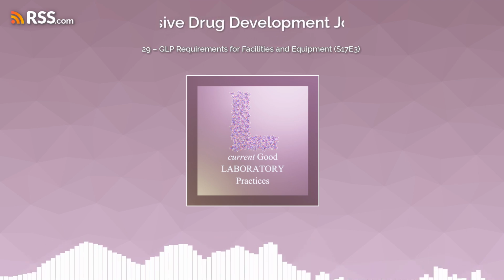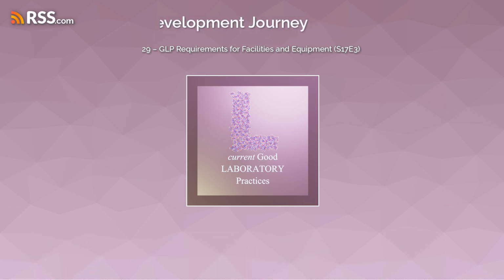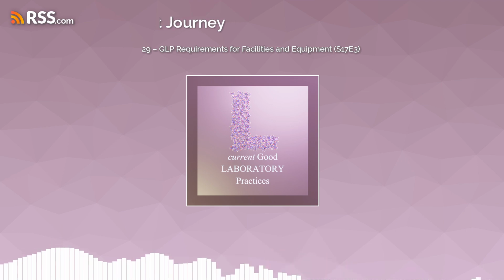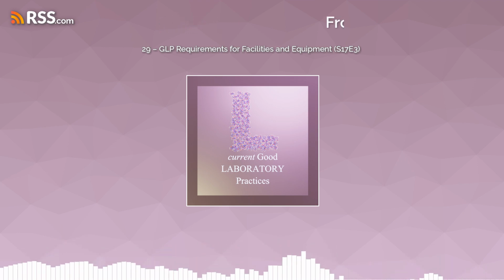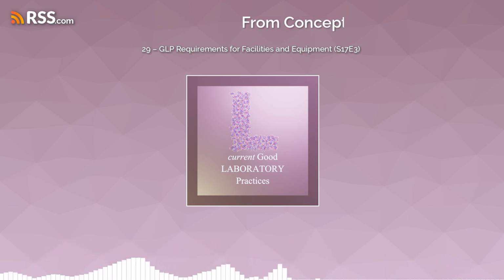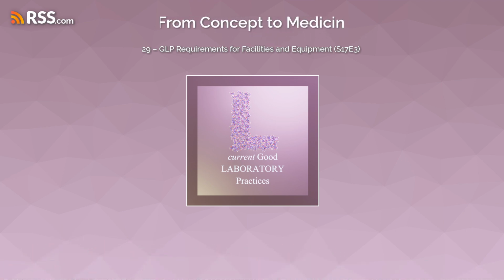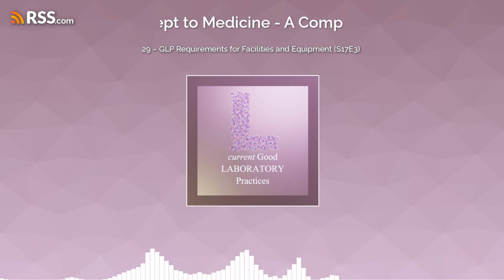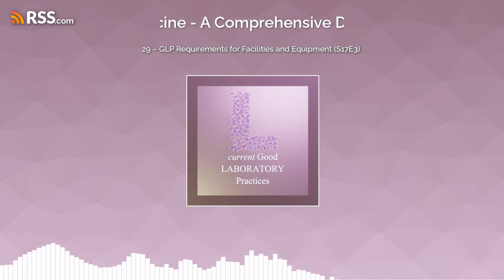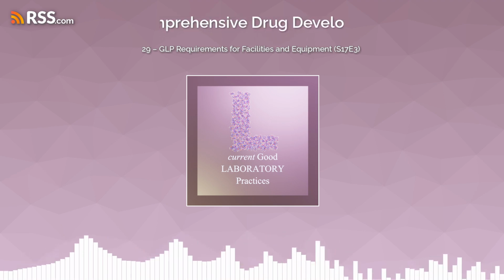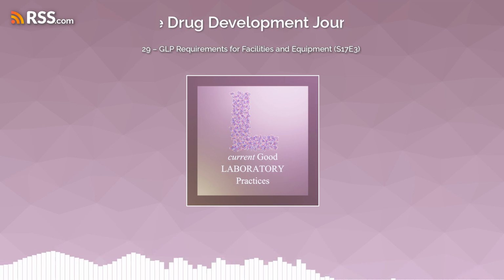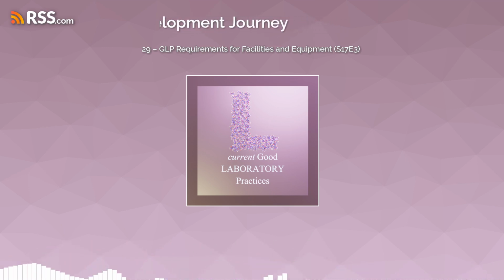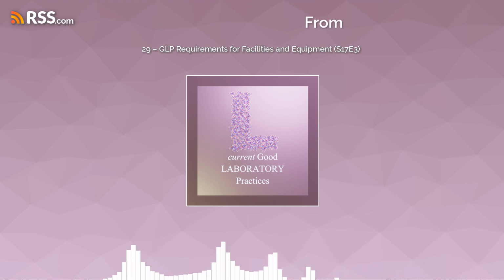Now, the transcript made a good point about different types of equipment. For big stationary equipment, you go through that whole DQ, IQ, OQ, PQ process. But for smaller, more portable instruments like pH meters or balances, it's a bit different. Right, because those get moved around the lab all the time. Exactly. So instead of doing the full qualification shebang every time, you calibrate them more frequently, maybe even before each use or at least daily. Makes sense. You wouldn't want to spend hours qualifying a pH meter every time you needed to check the acidity of a solution.